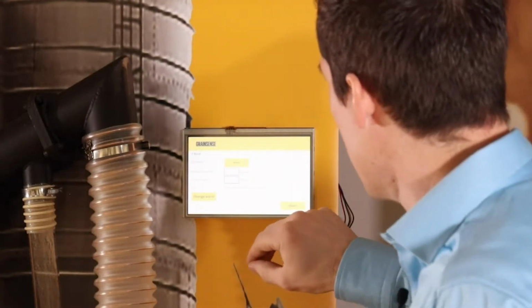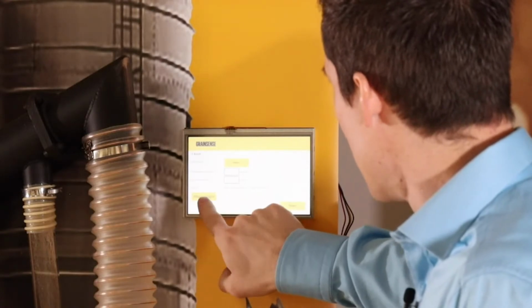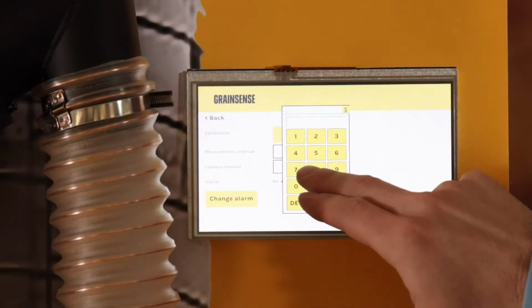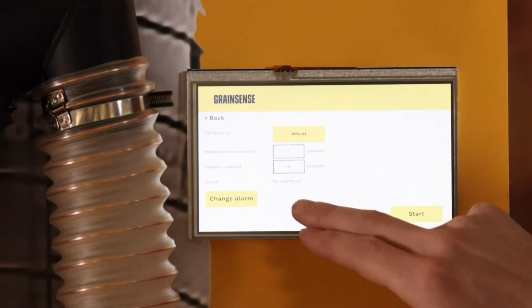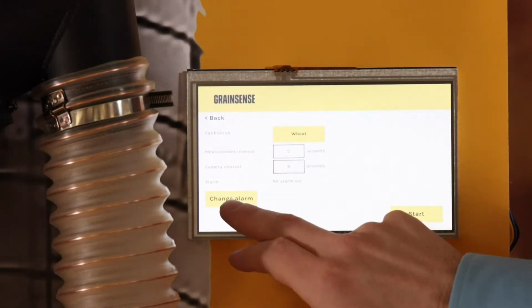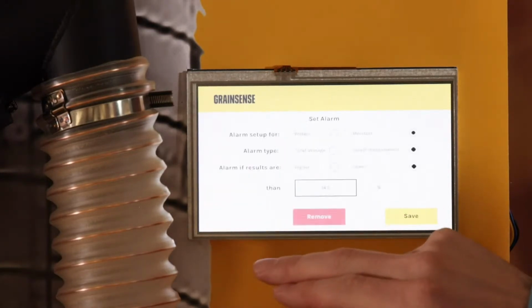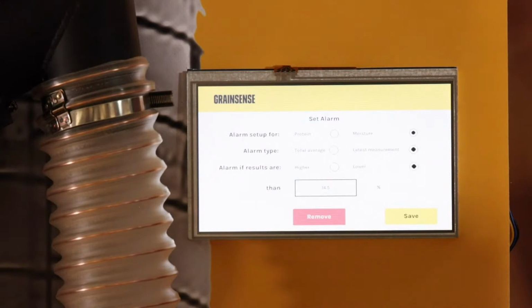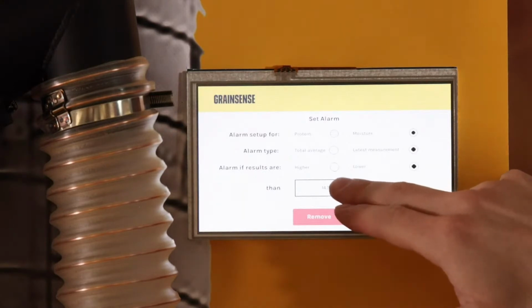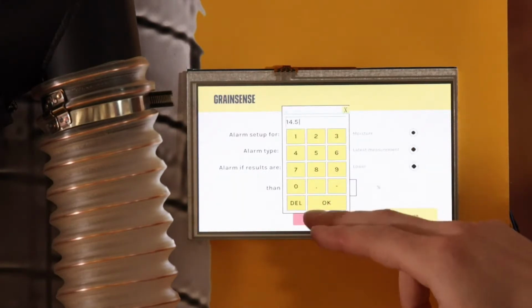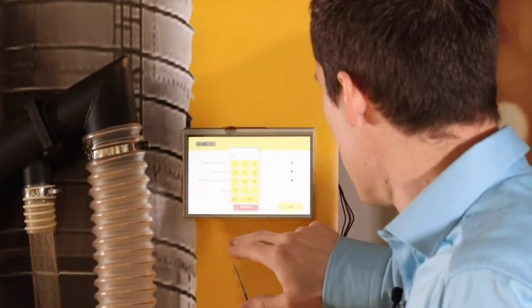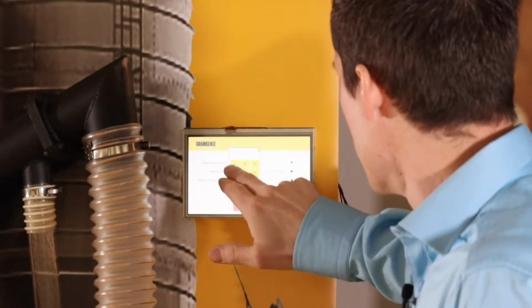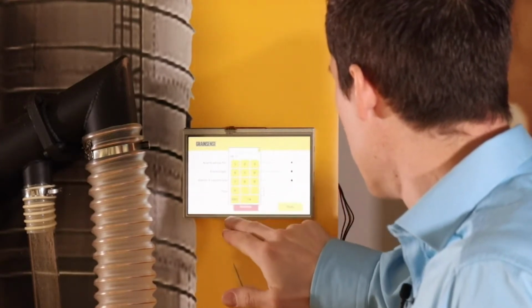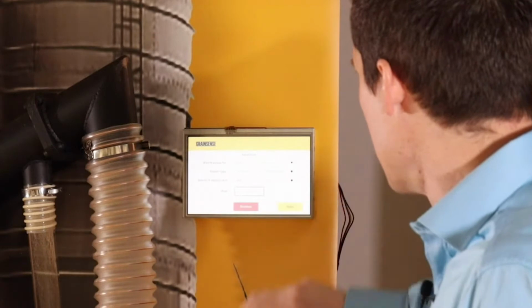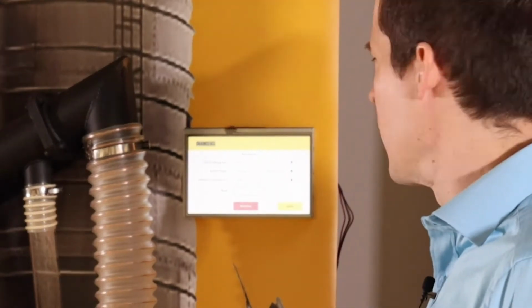And another thing that we can do here is change the alarm. So for example, when the GrainSense Flow Analyzer is installed in a dryer setting, this is a perfect application of this, where if you're drying grain, say if it's wheat starting out at 18% moisture and you want to bring it down to dry at 14.5% moisture, you can set the alarm so that it goes off once you have reached a moisture of 14.5%. And then that will help you, so you're not over drying your grain and spending more.